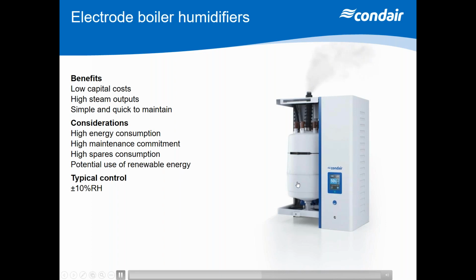So our electrode boiler, the heart of it is a polypropylene cylinder. And inside that cylinder are a series of electrodes. Here you can see them. When we get a demand signal, water fills up this cylinder to a level that's relative to the control signal. So if I've got 5 volts of a 0 to 10 volt signal, it'll fill up a certain amount and cover a certain proportion of those electrodes. And then current will be passed through the water, and we'll heat the water up and boil it, changing its state from a liquid into a vapor, and then steam merrily comes out of the top and goes through some flexible tubing or hard drawn copper into a steam pipe and is injected into the air handling unit.